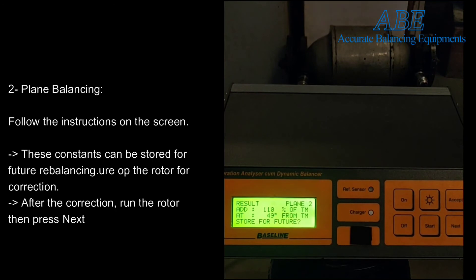In this case, for plane 2, the instrument is indicating that you need to add a weight that is 110% of the trial mass, and it is to be added at a position in the increasing direction, 49 degrees from the trial mass.